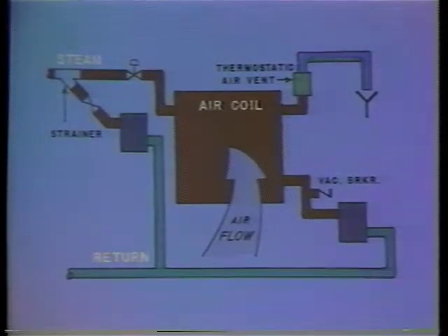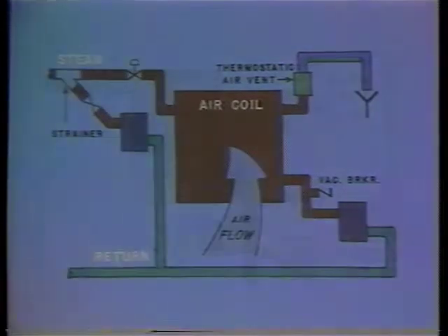At times when the heating load to the coil is reduced, the steam control valve will modulate, causing a reduction in steam pressure to the coil. The steam pressure may be reduced to a point where the collapsing steam in the coils generates a vacuum at the trap. When this happens, the integral vacuum breaker in the F&T will open, breaking the vacuum by admitting air. With the vacuum broken, gravity will cause condensate to flow if a drip leg of sufficient height has been provided. This, of course, will prevent flooding of the coils.